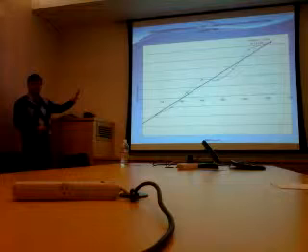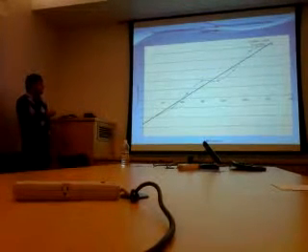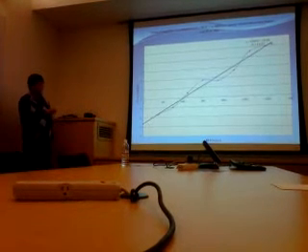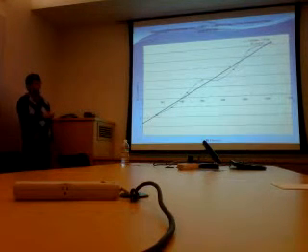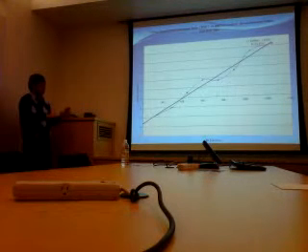This graph is in the contact mode. This is data that we collected in the contact mode. As you see, if we plot the BUA, the broadband ultrasound attenuation, versus BMD, you get a positive linear slope with an R squared value of 0.9797. So as density increases, the BUA increases as well.